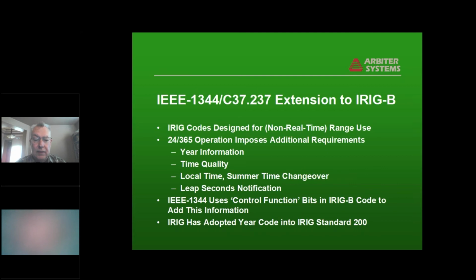We need advance warning of things like local time changes, summertime changeover, and notification of leap seconds. And all that information has been added to the IRIG B code by using 27 control function bits, which were allocated in the original IRIG standard and left to individual ranges or industries to use as they saw fit. IRIG standard 200, which standardizes the IRIG B and all of the other IRIG time codes, actually adopted the 8-bit 2-digit year code that IEEE developed, as an optional use of 8 of the control bits.